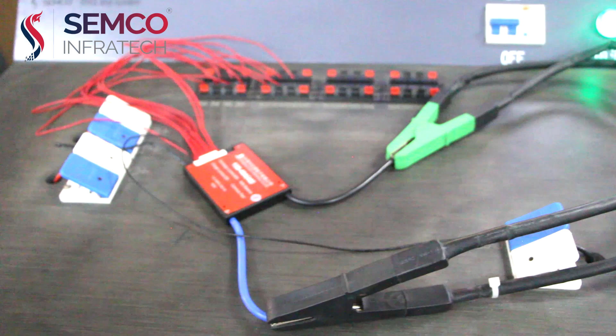The task of the battery management system is to ensure optimal use of the residual energy present in a battery, in order to avoid loading the batteries into deep discharge and over voltage, which result from extreme fast charge and extreme high discharge current.